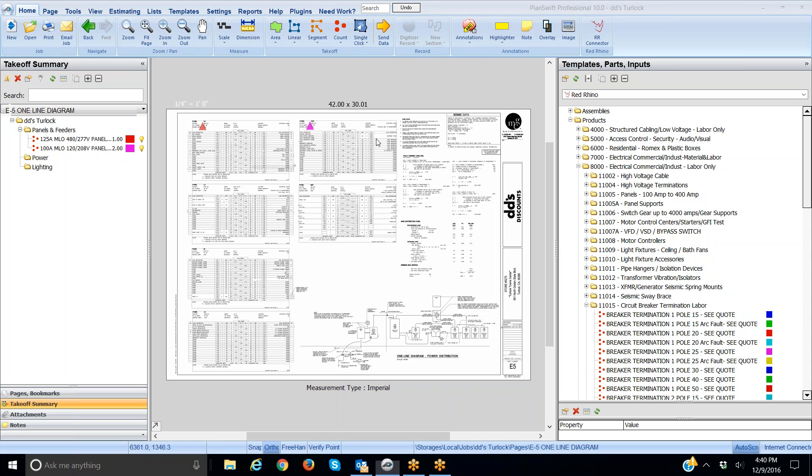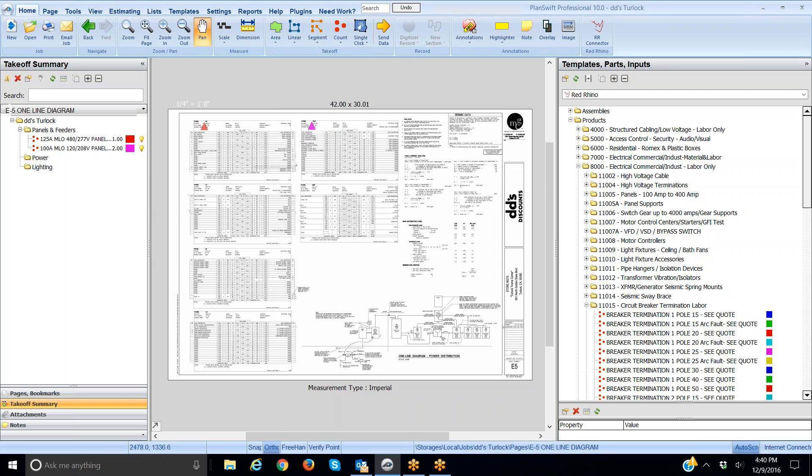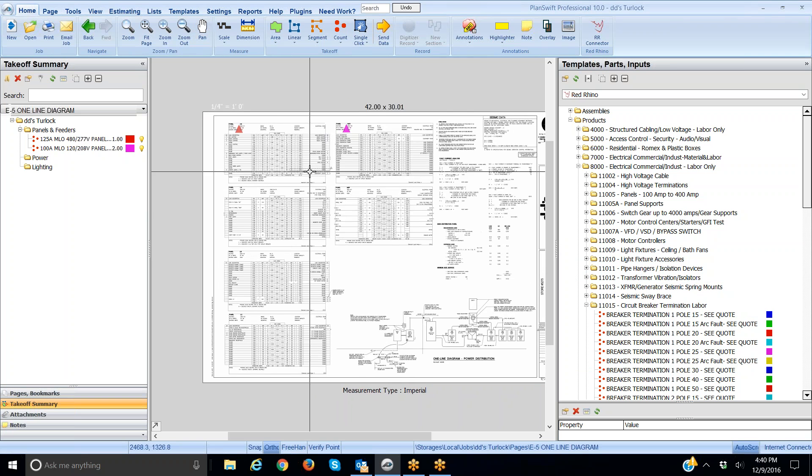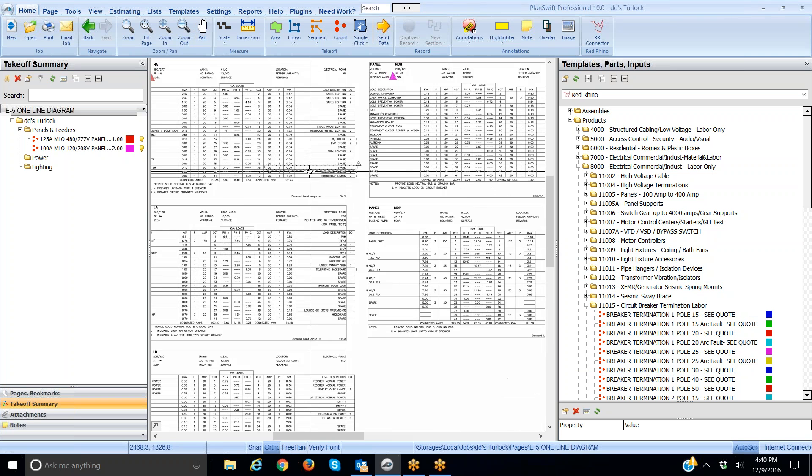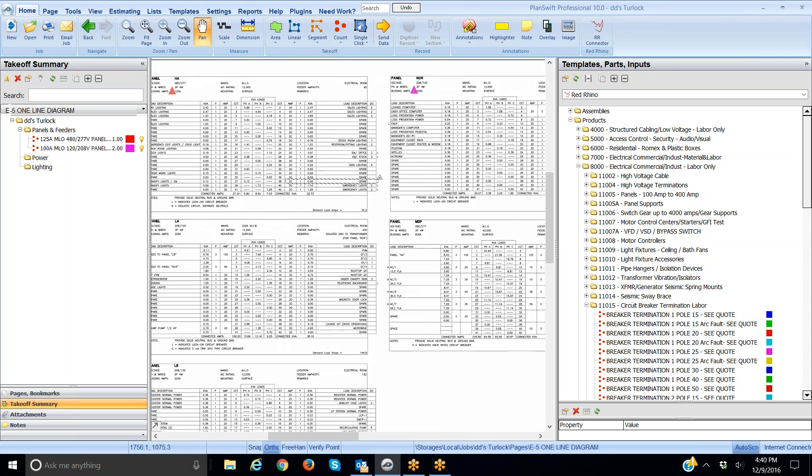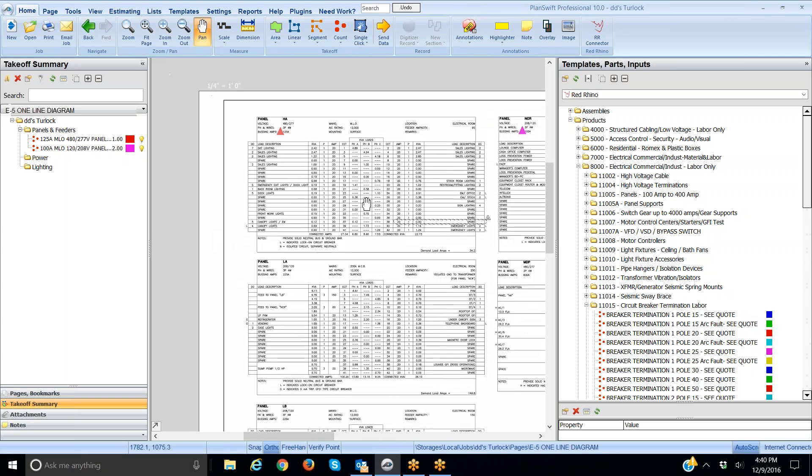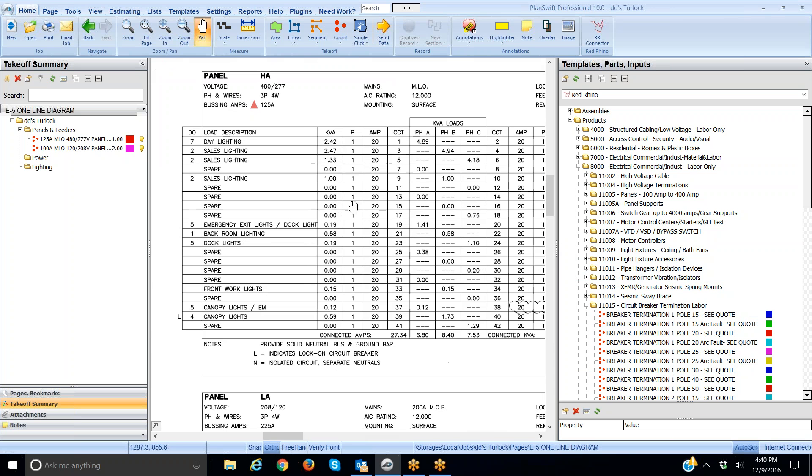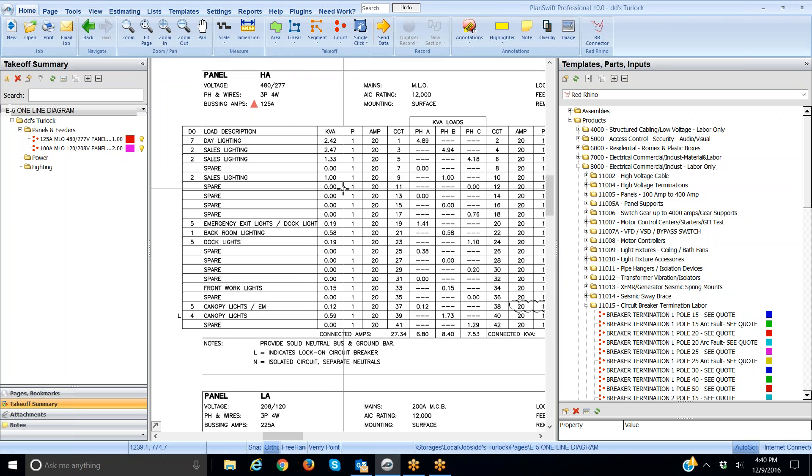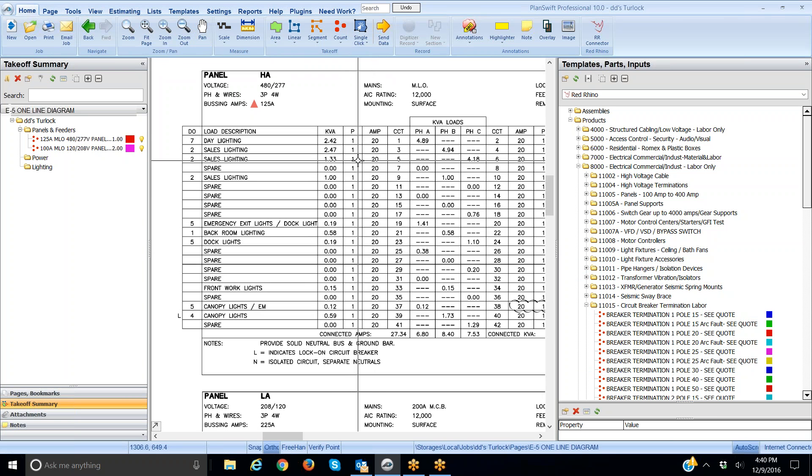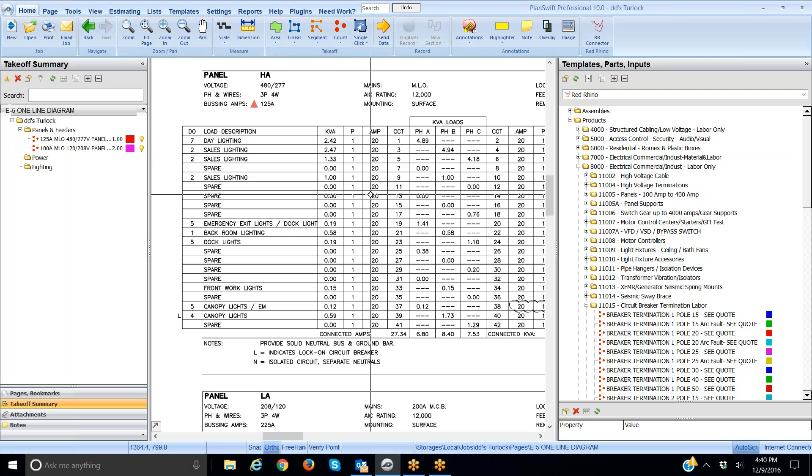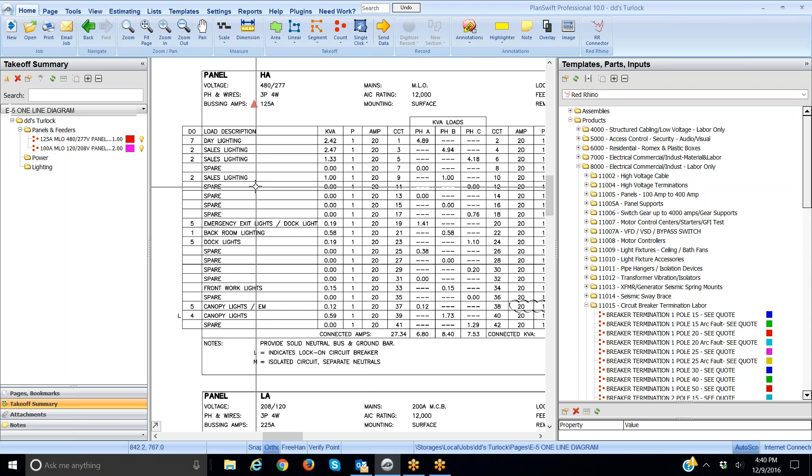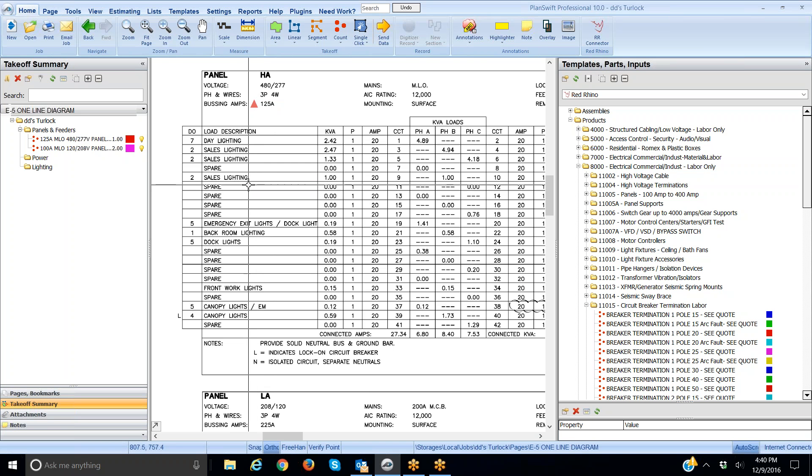I'm going to zoom in here again. I'm not going to do all these but I'm just going to show you the idea. I see that this panel has a whole ton of 20 amp one pole circuit breakers. I want to explain something. You don't need to take off the spare circuit breakers. Right now we're only capturing labor for termination. So when a breaker is a spare you don't have to terminate wires to it. Therefore you don't have to count it for labor.